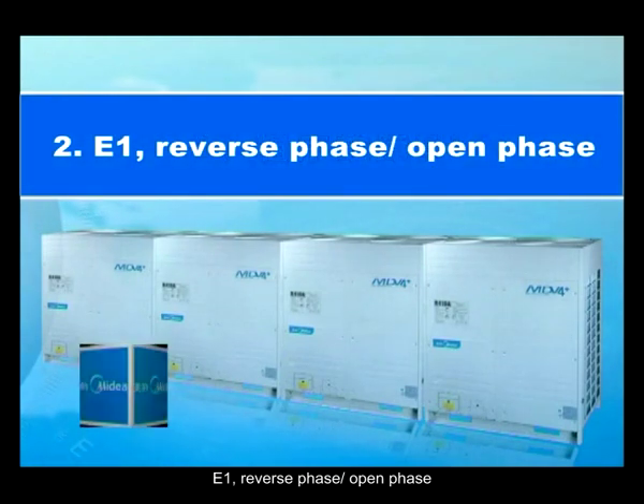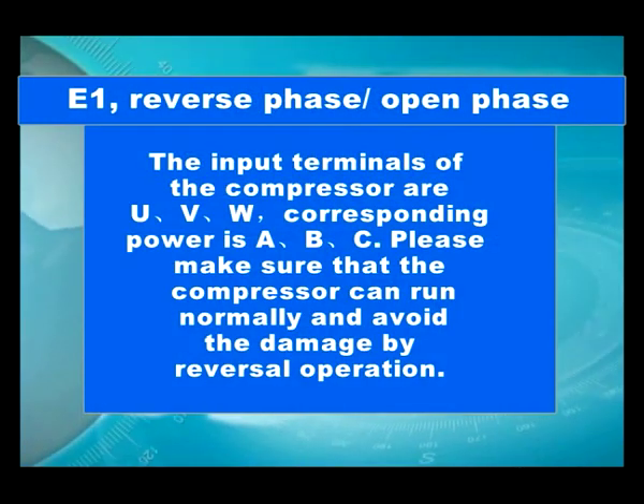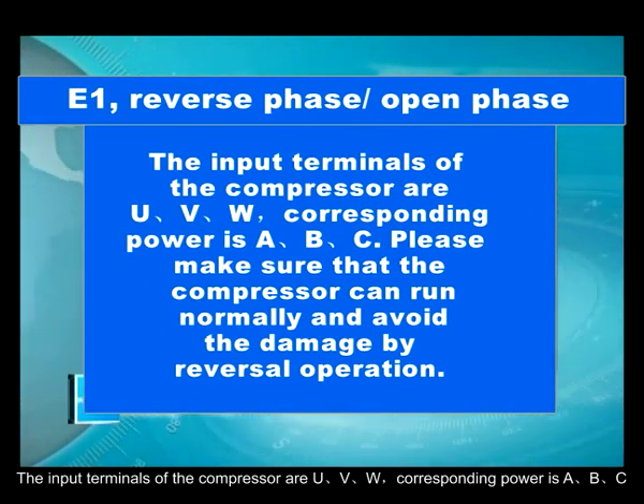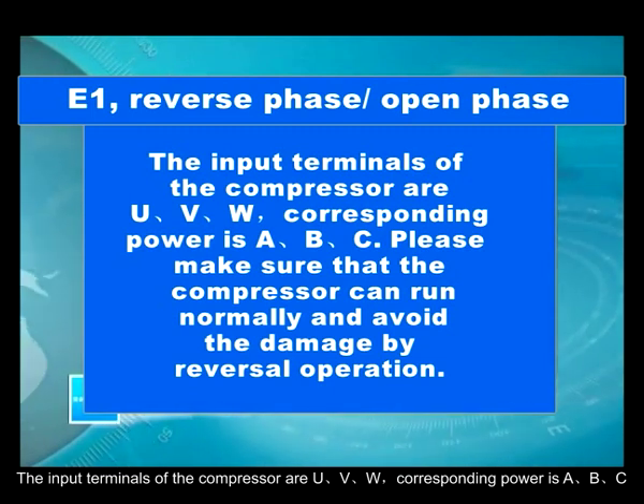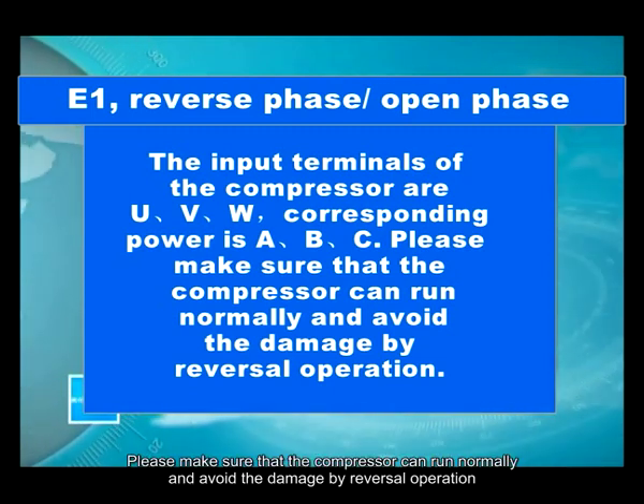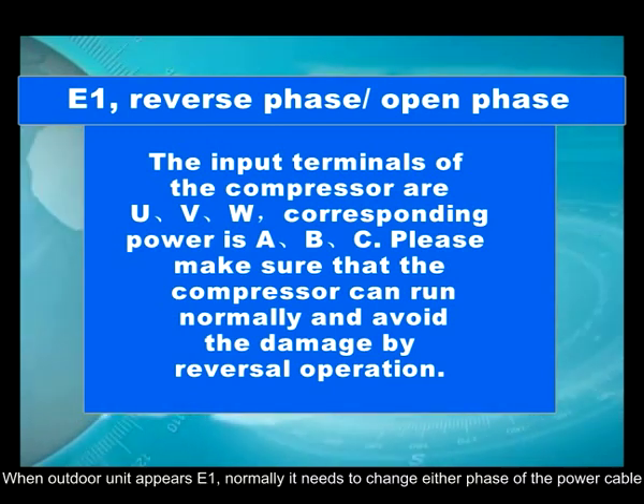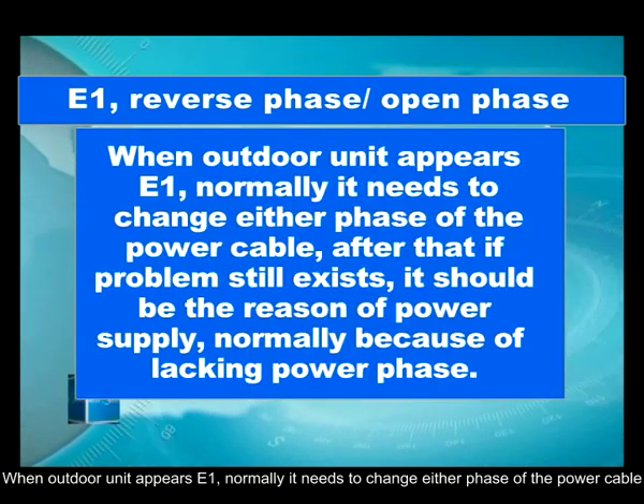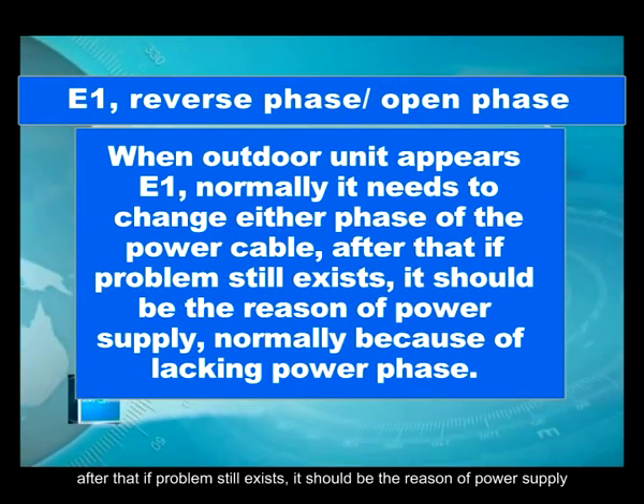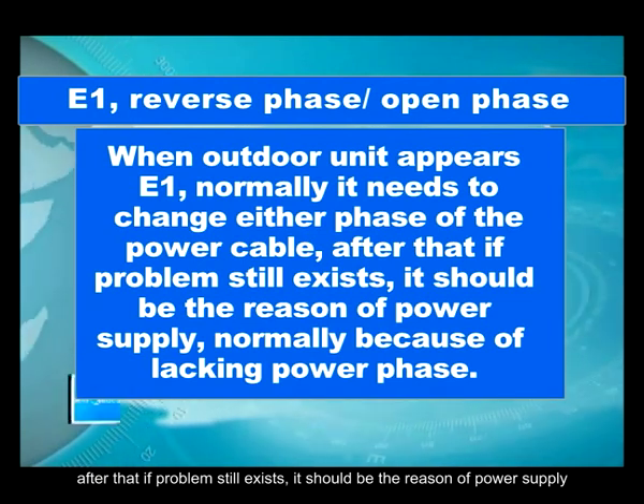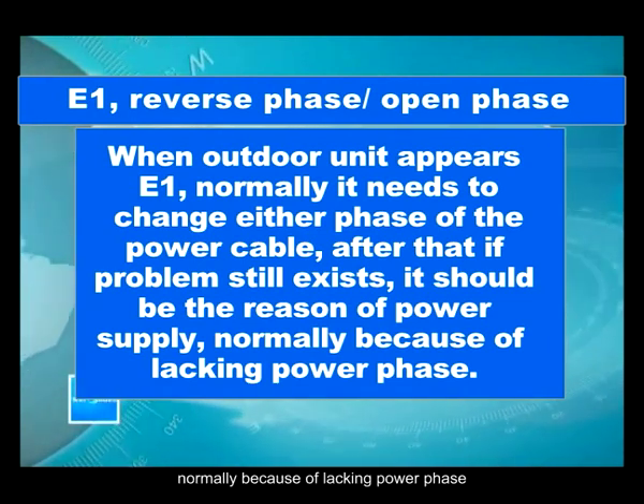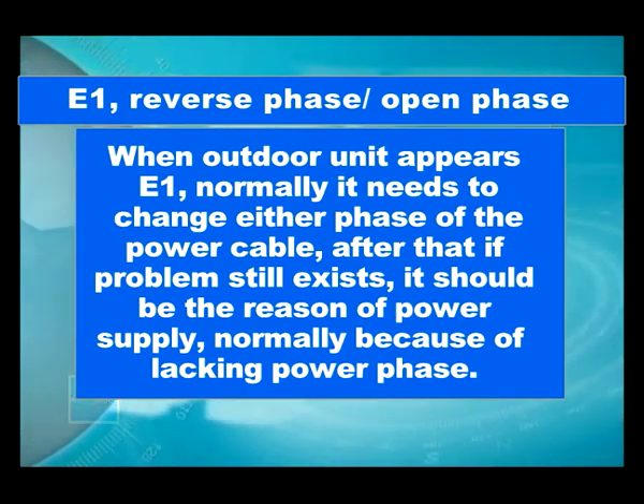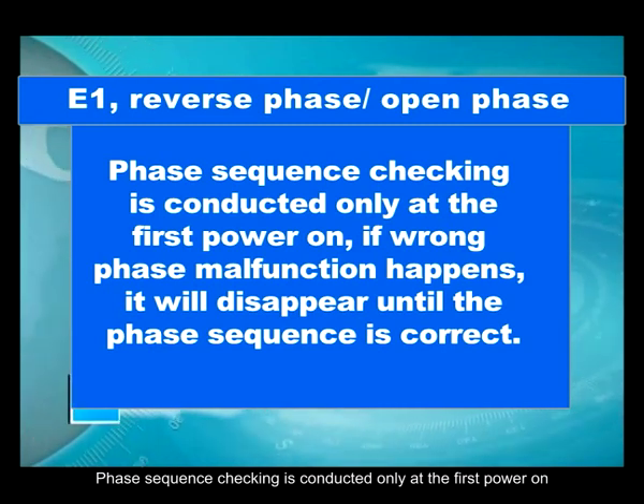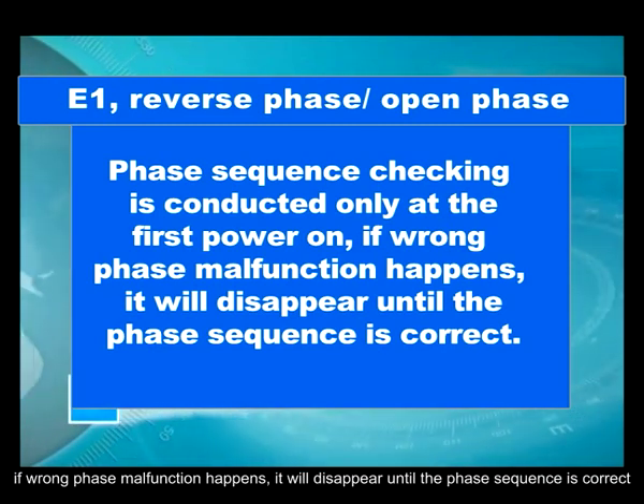E1. Reverse phase / open phase. Input terminals of the compressor are U, V, W. Corresponding power is A, B, C. Please make sure that the compressor can run normally and avoid the damage by reversal operation. When outdoor unit appears E1, normally it needs to change either phase of the power cable. After that, if problem still exists, it should be the reason of power supply, normally because of lacking power phase. Phase sequence checking is conducted only at the first power on. If wrong phase malfunction happens, it will disappear once the phase sequence is correct.